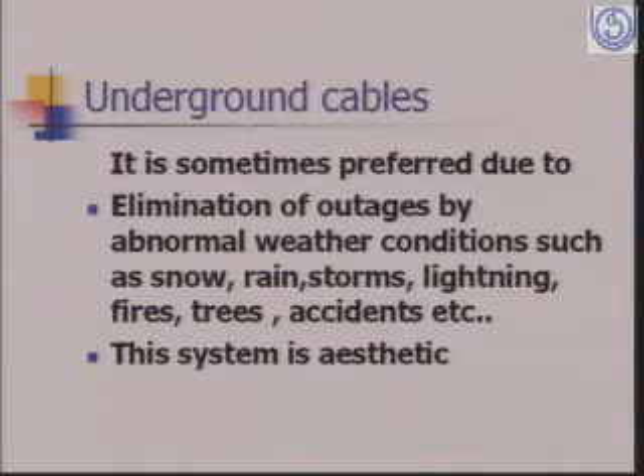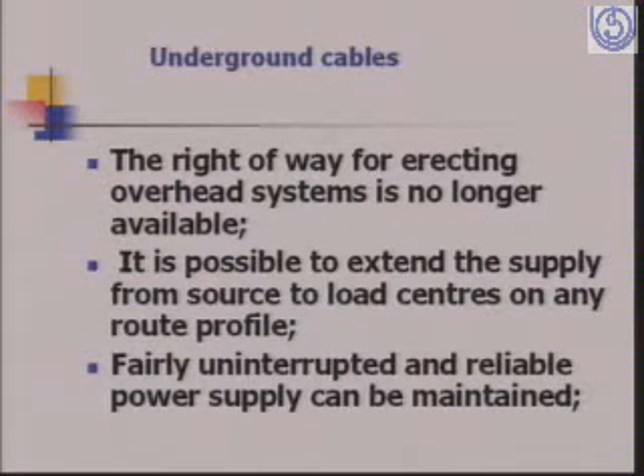Then this system is more aesthetic. The overhead lines are not very aesthetic. They are on the roadside, but if we use underground cables, then we cannot see them. Then the right of way for erecting overhead systems is no longer available. Then also we use underground cables, and it is possible to extend the supply from source to load center on any route profile. Overhead lines are generally taken on the sides of the roads, but this can be extended on any route profile, and a fairly uninterrupted and reliable power supply can be maintained through underground cables.